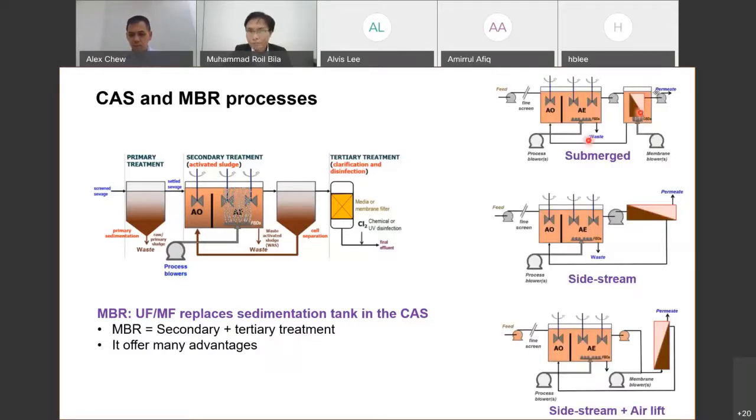There are many different configurations of MBR. For example, on top, it's called a submerged MBR in a separate tank. Basically, we place the membrane in the tank here, and then we use a pump to draw the permeate. So this is the submerged configuration. We can also have a side stream configuration where we use a cross flow velocity. And another configuration is side stream with airlift. Airlift is basically using air to promote the flux.